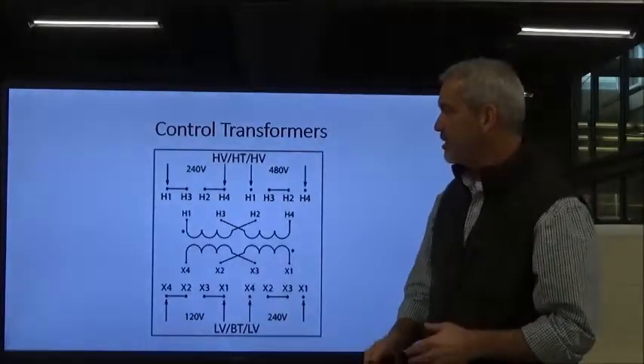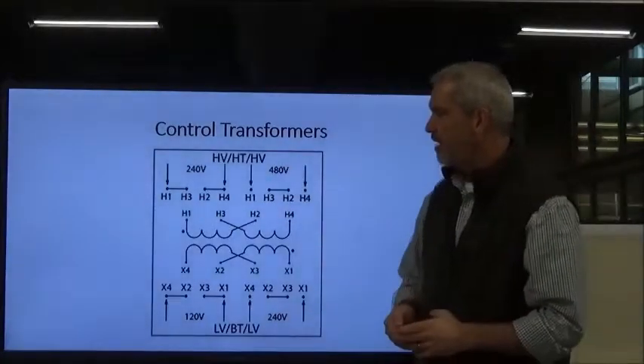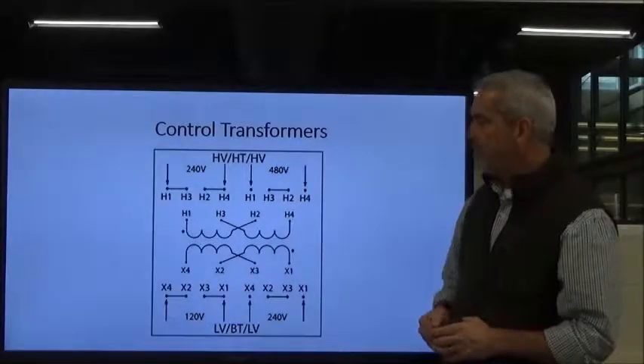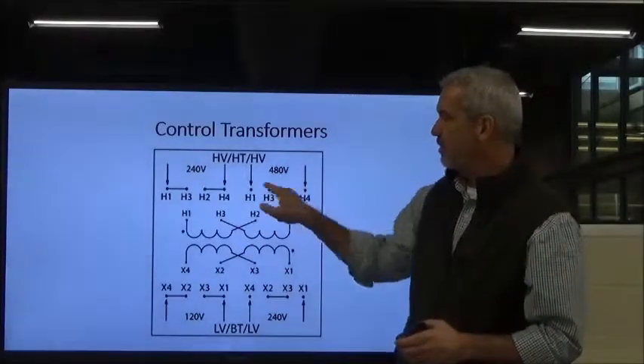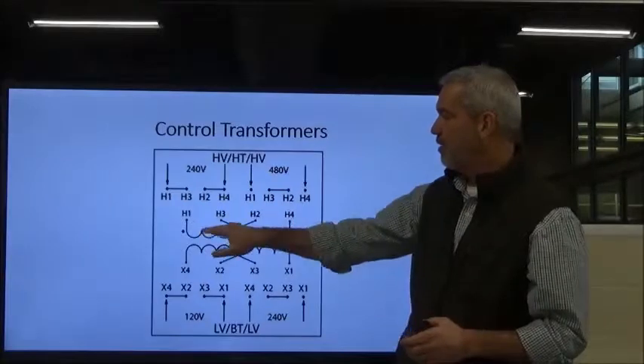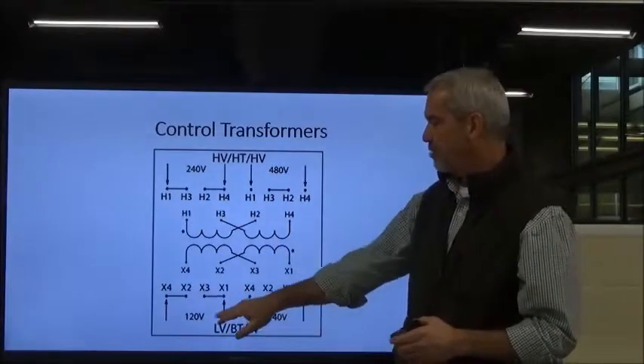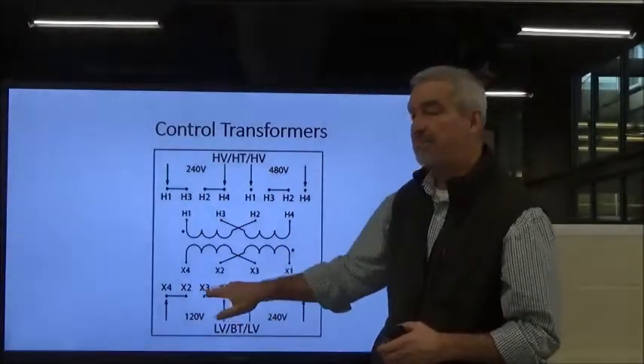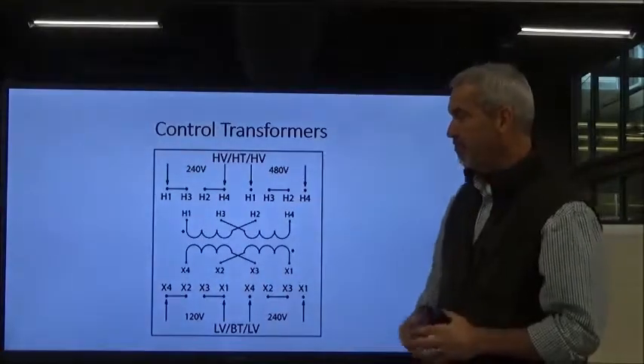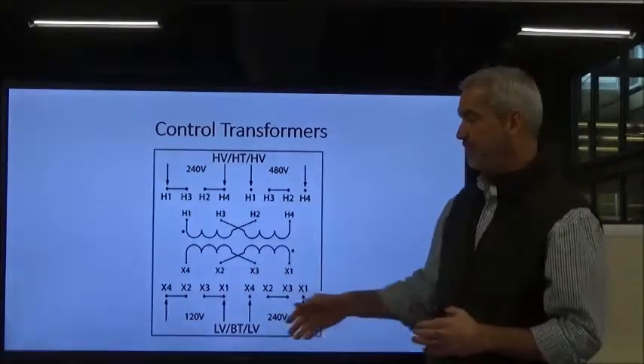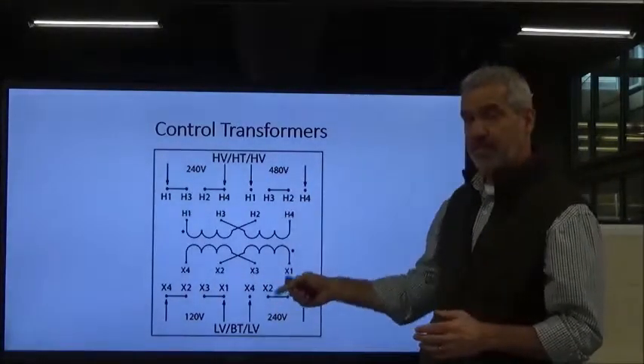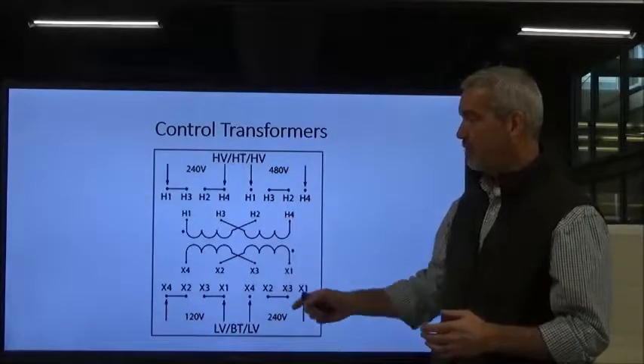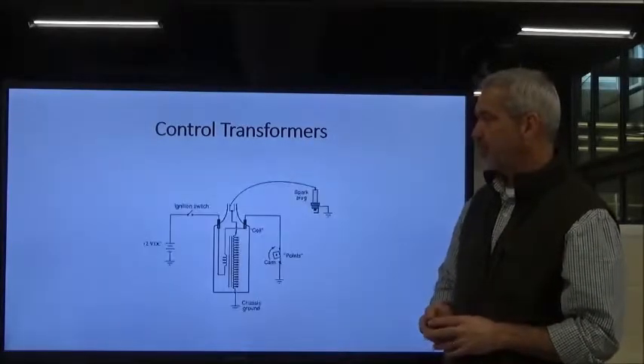This is a schematic of the one you'll be working with in the lab. You can configure it for 208, 240, or 480 on the primary side, and 120 or 240 on the output, depending on where you put your jumpers. That makes a big difference on your output voltage. My point is that these transformers are configurable.